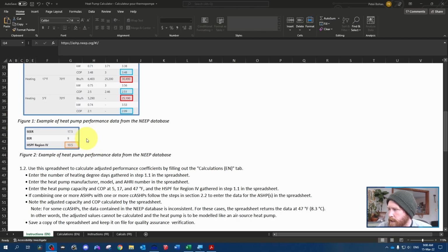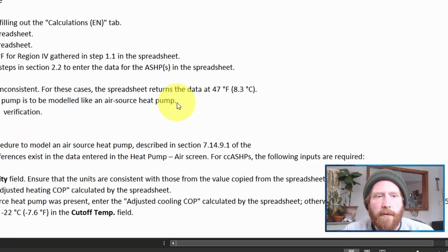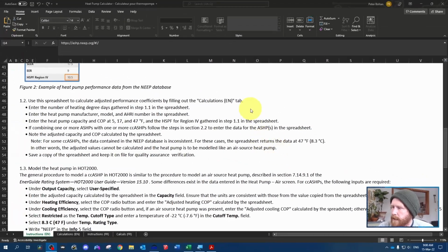the calculation sheet. And then there's a note here that says, for some cold climate air source heat pumps, the data contained in the NEEP database is inconsistent. For these cases, the spreadsheet returns the data at 47 degrees Fahrenheit. In other words, the adjusted values cannot be calculated and the heat pump is to be modeled like an air source heat pump. So I myself have not run into this issue yet. If you do, let me know what it looks like. I'd be curious to see.